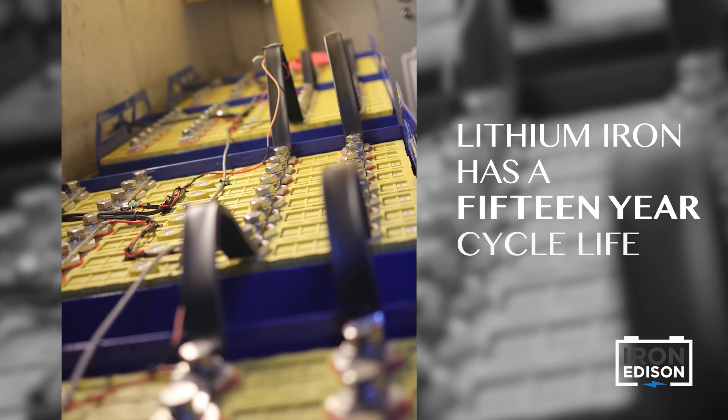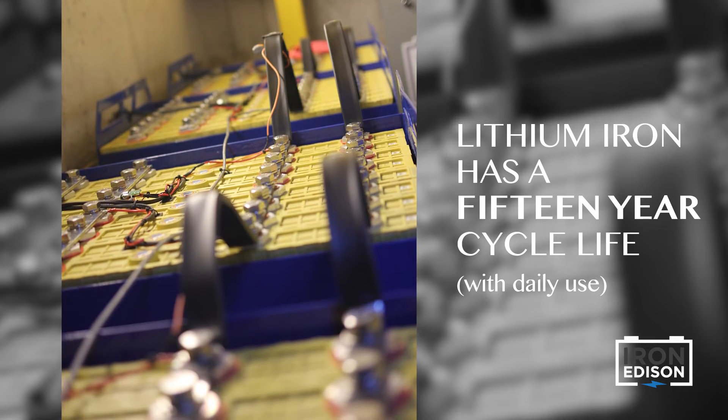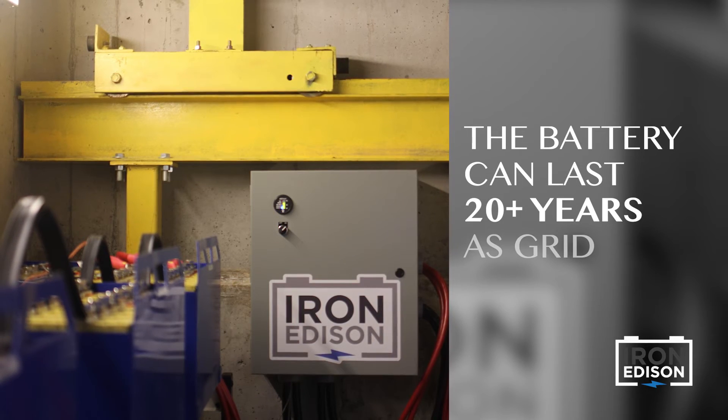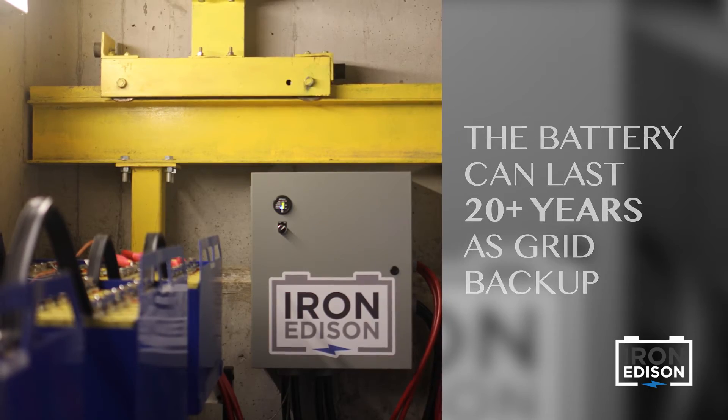This lithium iron battery is designed to last for 15 years of daily use. In this particular application, the customer is not cycling the battery every day, so we could expect this battery to last for two to three decades or more.